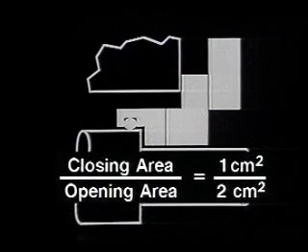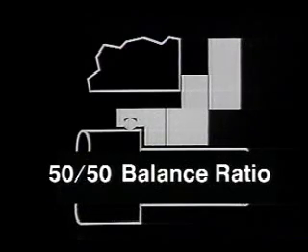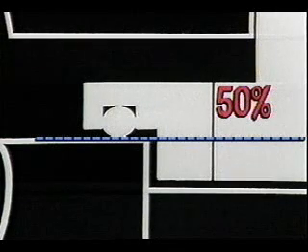If we compare the closing area to the opening area, we find a 50 percent ratio. This area ratio of 50 percent is called a 50-50 balance ratio. This means that 50 percent of the opening area is exposed to the closing force.